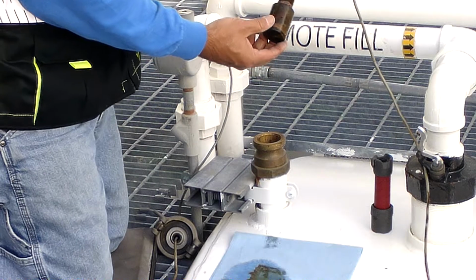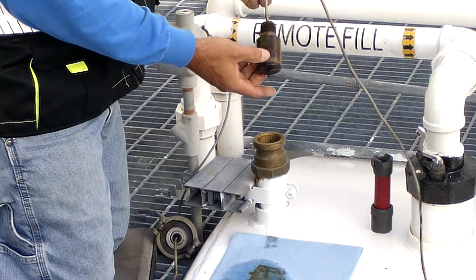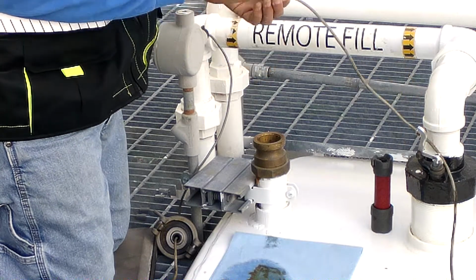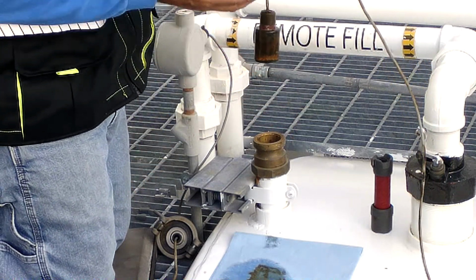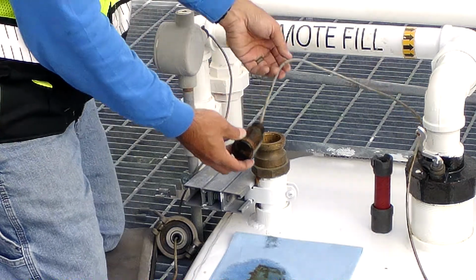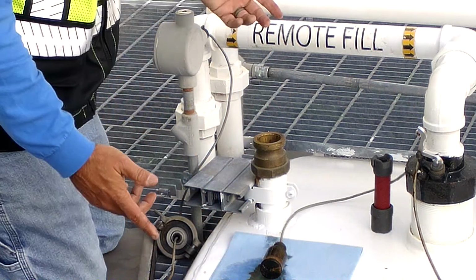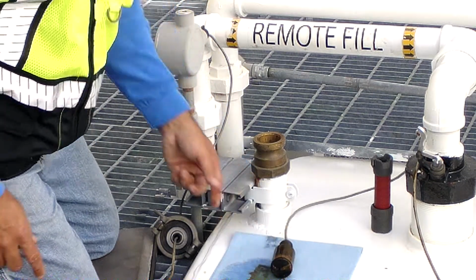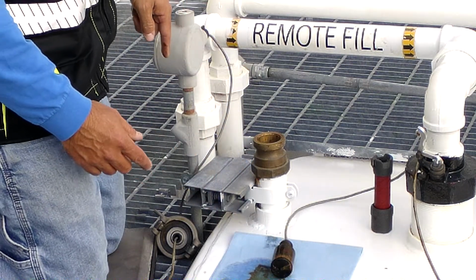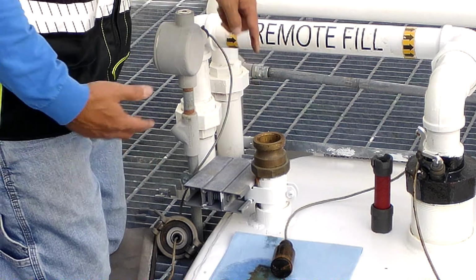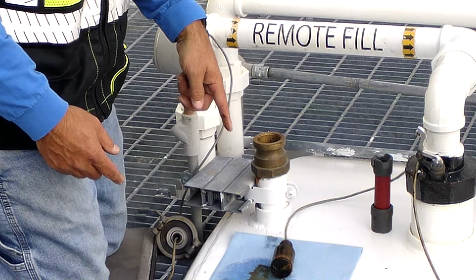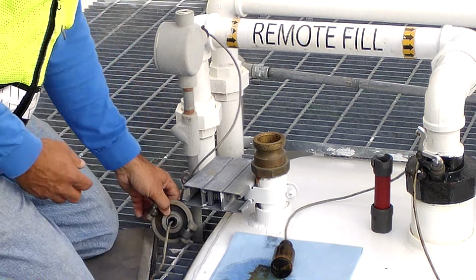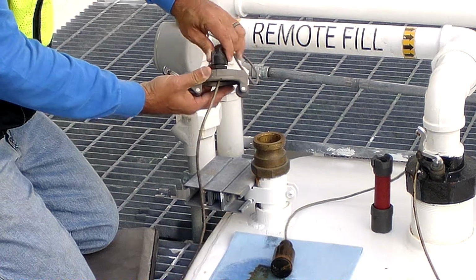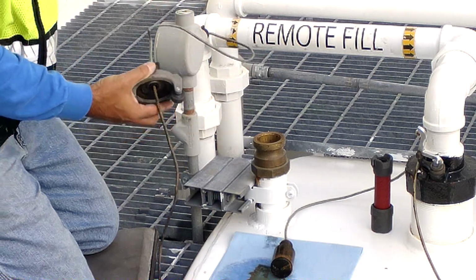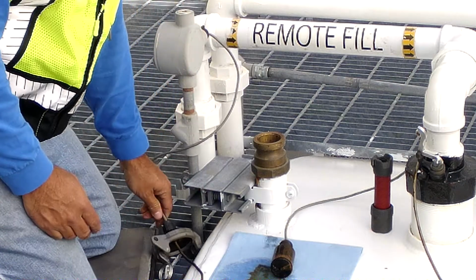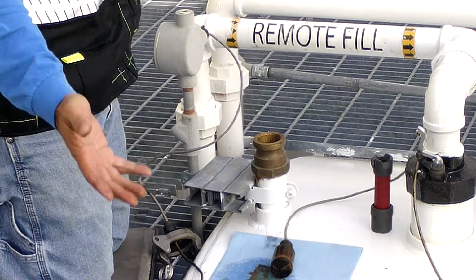The next thing with this sensor, if it wasn't already in alarm, is I would want to verify by flipping it up and down or putting it in a test bucket of water to verify that it activates the alarm in the remote console. The last thing with a sensor is to make sure that the cable and the sensor actually go all the way down to the bottom of the tank. So I would need to measure down the diameter of the tank and make sure that this wire is going all the way down. A lot of facilities sometimes remove the wire and extend it up with this cord grip and then pull it up so that it keeps the sensor out of the water. After that is all done and we verified this, we need to reinstall it.